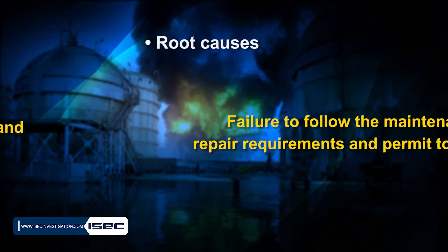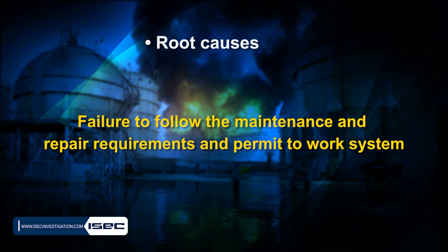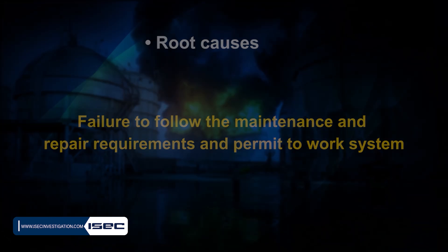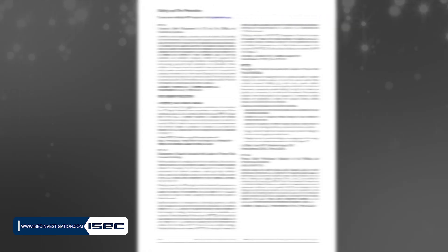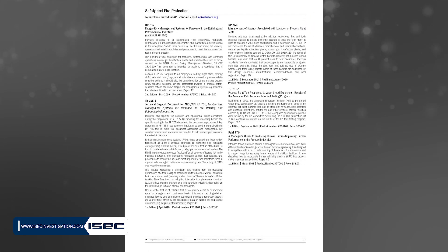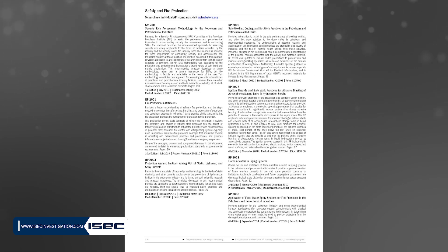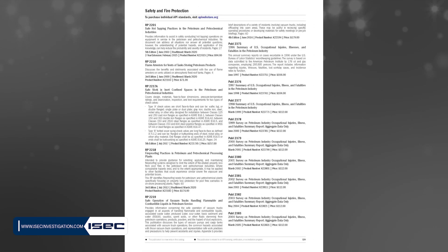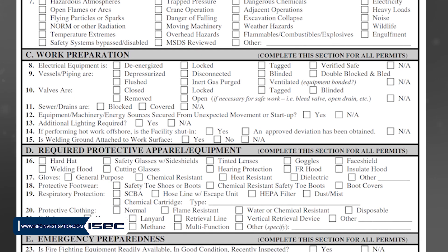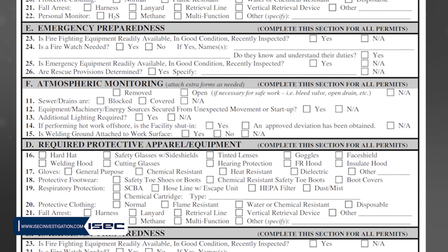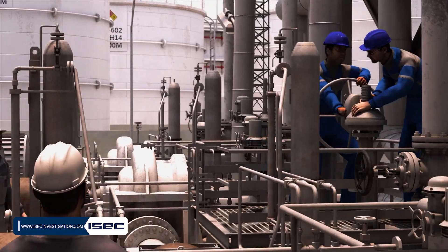Failure to follow maintenance and repair requirements and the permit to work system. For any repair work, an instruction must be prepared according to the risks involved, and the presence of the repair manager is required for inspection and safe operation. According to the mechanical isolation instructions, the standard blind flange should be fully bolted. A work permit had been issued for replacing the electric motor of pump C with a manual gearbox, but at the time of the work, the gearbox of pump A was removed without any work permit.